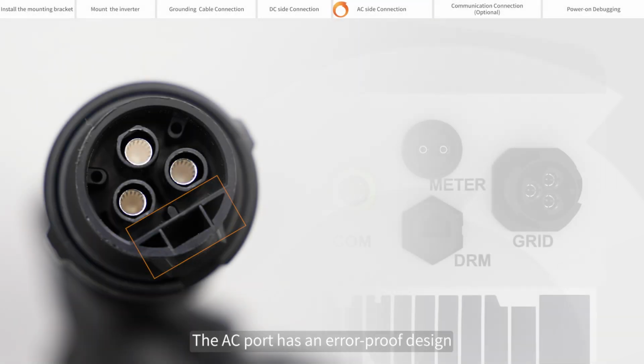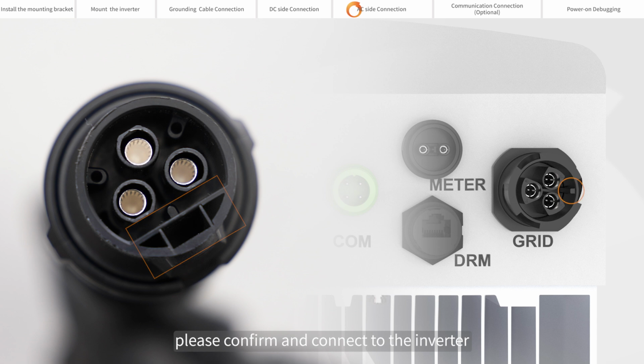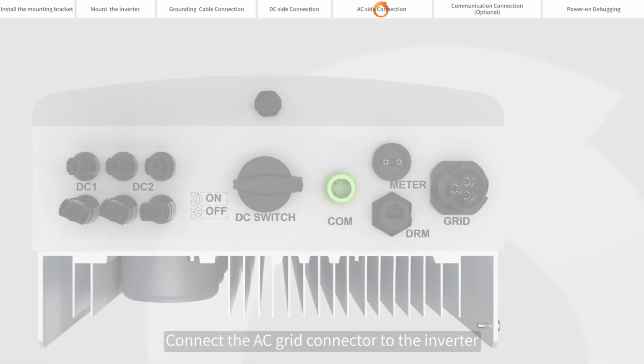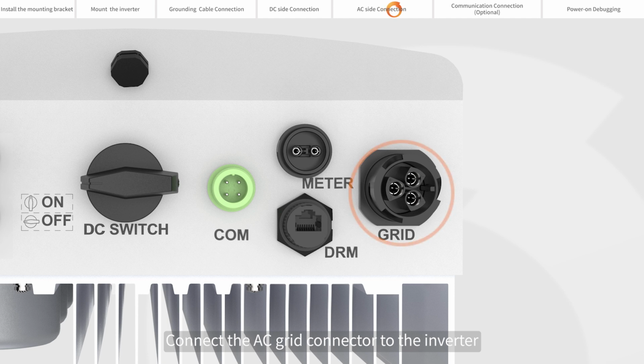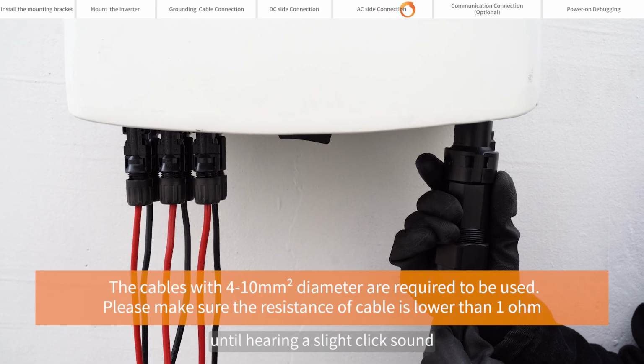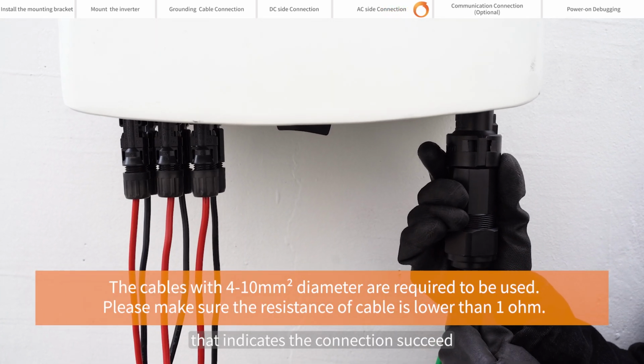The AC port has an error-proof design. Please confirm and connect to the inverter and tighten the external latch. Connect the AC grid connector to the inverter until you hear a slight click sound that indicates the connection succeeded.